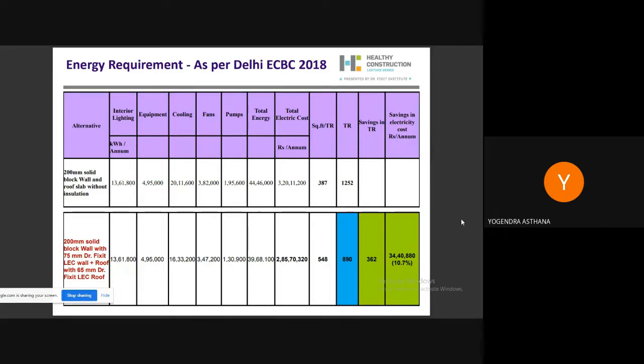After this insulation, there will be no change in interior lighting energy consumption. Equipment consumption will also not change. They both are the same, but the change will come in the energy requirement for cooling, fans and pumps, which are used for handling these cooling systems.